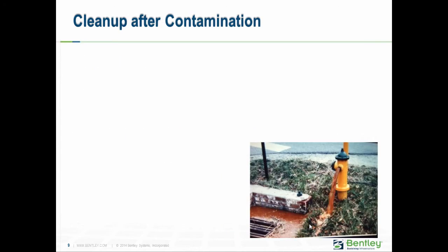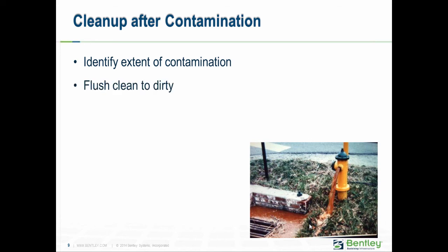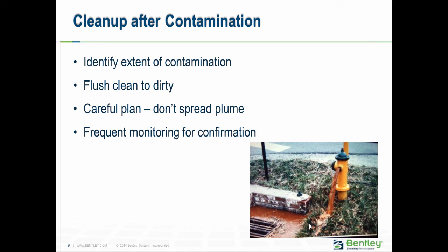There are cases of known or suspected contamination — possibly a backflow event in the distribution system. The success of flushing depends primarily on identifying where the contamination is. There's usually some plume of contamination. If you have a good handle on what caused the event, you can do a much better job figuring out how to flush. The rule is flush from clean water to dirty areas, but you need careful planning. You don't want to open a hydrant away from the plume and draw that contaminated plume further into the system. Modeling can help evaluate what-if scenarios. Also monitor for contamination while flushing in the field.